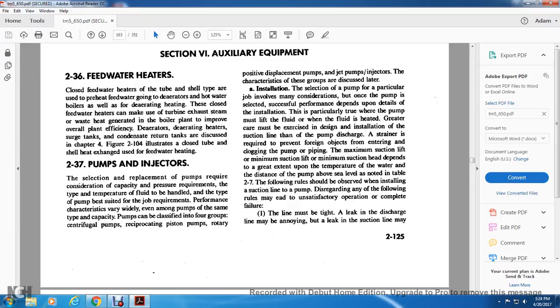2-37 Pumps and injectors. Selection and replacement of a pump requires consideration of capacity, pressure requirements, the type and temperature of the fluid to be handled, and the type of pump best suited for the job. Performance characteristics vary widely even among pumps of the same type and capacity. Pumps can also be classified in four groups: centrifugal pumps, reciprocating piston pumps, rotary pumps and positive displacement pumps, and jet pumps and injectors. Characteristics for these groups are discussed later.